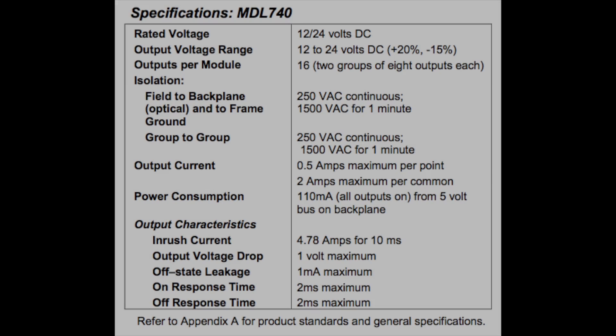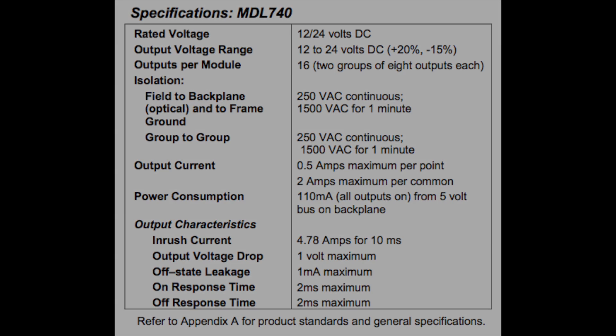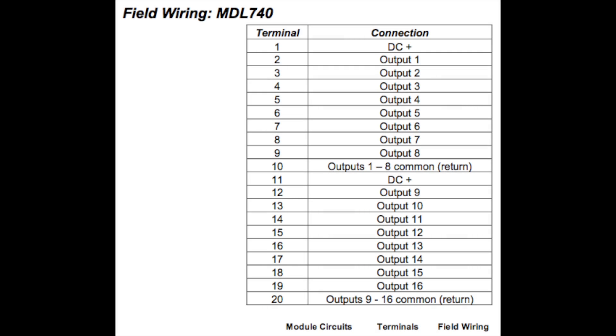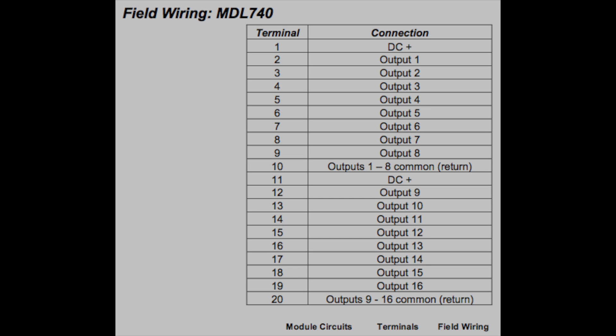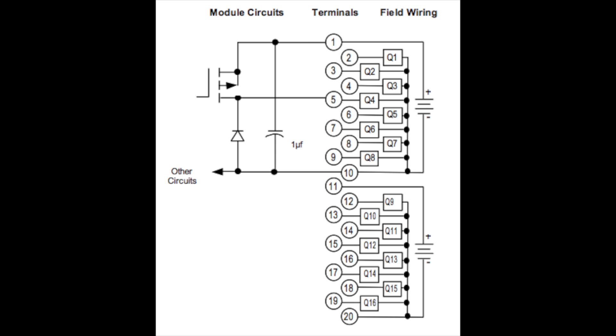I have here an IC694MDL740. This is a 16 point, grouped, positive logic, 12 to 24 volt DC output. So you can be using 12 volts DC to 24 volts DC.